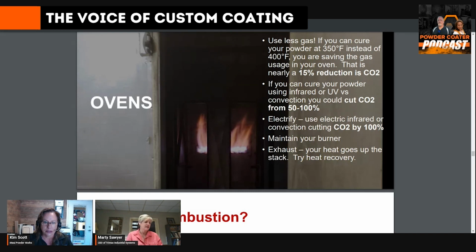And I don't put it in here, but I always like to mention this because I've started to see a trend in some of the more economical ovens out there on the convection side, the batch side: there's a shortcutting on the purge when you start it up. It's supposed to start up the oven faster. Can you save money? Less turns.